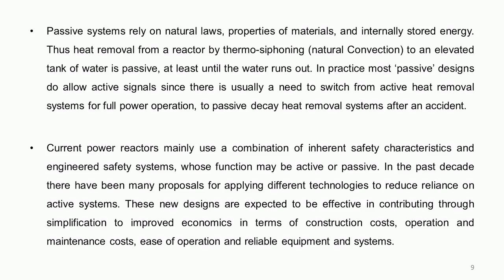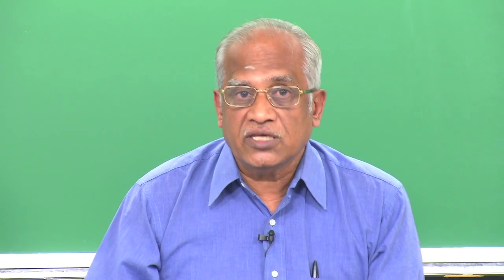Most current power reactors use a combination of intrinsically safe characteristics — like the negative reactivity coefficient or negative feedback coefficient — and engineered systems which may be active or passive. In the past decade many proposals for applying different types of technology are being brought out to reduce reliance on active systems. However, these new designs need to be cost-effective, prove their reliability through operating experience, and be simple in their complexity of operation.